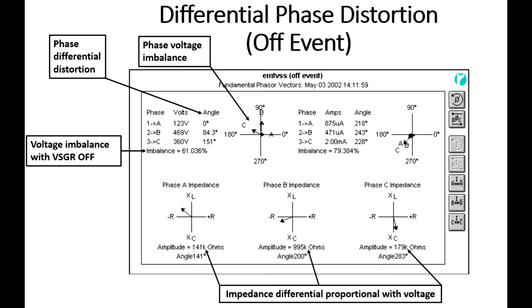Here's some additional data from that event. The power system had the three voltages we looked at in the previous slide: 123 volts for phase A, 469 for B, 360 volts for C. We see that the angle was 0, 84, and 151. They should be 120 degrees from each other. We see that graphically shown on the phase voltage imbalance, the three little arrows here, electrical vectors called phasors. And just below that, the voltage imbalance was 61%. On the bottom, we see the three significantly different impedances. What that is indicating, as the impedance becomes lower and lower, it's significantly easier for voltage to flash over.